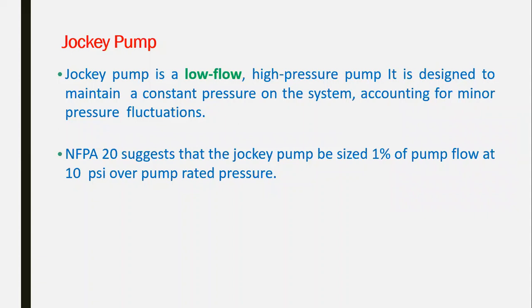The other one, so this is a second type of the valves. The other accessory in the fire system is the jockey pump. And the jockey pump, as we said, is a small pump to maintain the pressure, and it is working with a pressure difference, when the pressure difference is 5 to 10 psi. The size of the pump itself, on average, is 1% of the overall fire pump size. So it's a small pump in discharge and capacity, but it is producing a high pressure for the network. So the pressure for this one has to be 10 psi over the pump rated pressure.